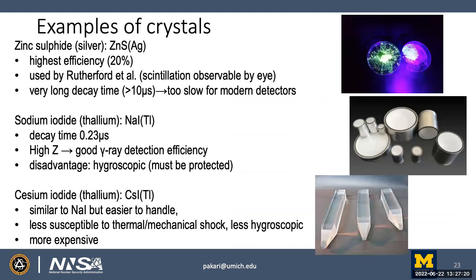Zinc sulfide is a classic scintillator with very high light yield efficiency — used by Rutherford because he could see scintillation by eye — but its decay time is beyond tens of microseconds, which is too slow for modern systems. More modern detectors include sodium iodide doped with thallium, NaI(Tl), giving intermediate energy states in the bandgap for luminescence, with decay time under one microsecond and high Z for good gamma detection efficiency. Its disadvantage is that it is hygroscopic and must be protected with casings. An alternative is cesium iodide doped with thallium, CsI(Tl): easier to handle, less susceptible to thermal and mechanical shocks, less hygroscopic, but more expensive.